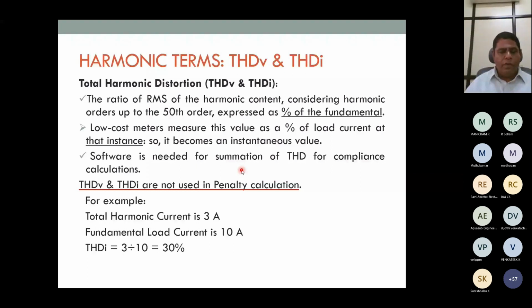Those meters will not measure the summated value of TDD or THDV. It will be giving an instantaneous value, which is an erroneous measurement. Please do not take any action based on those values, because it is only what the harmonic current or voltage is at that instant, which is not the thing mentioned in our regulation. So it is totally different. So low cost meters will not be useful for finding out proper harmonic compliance.